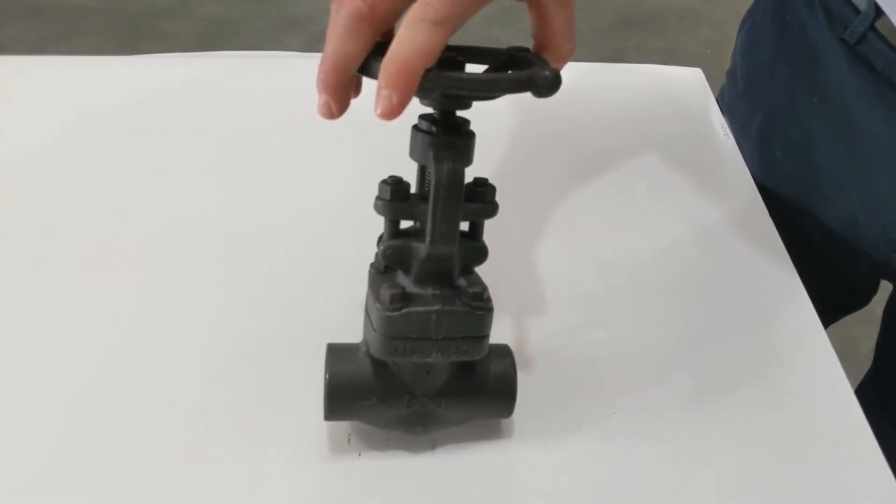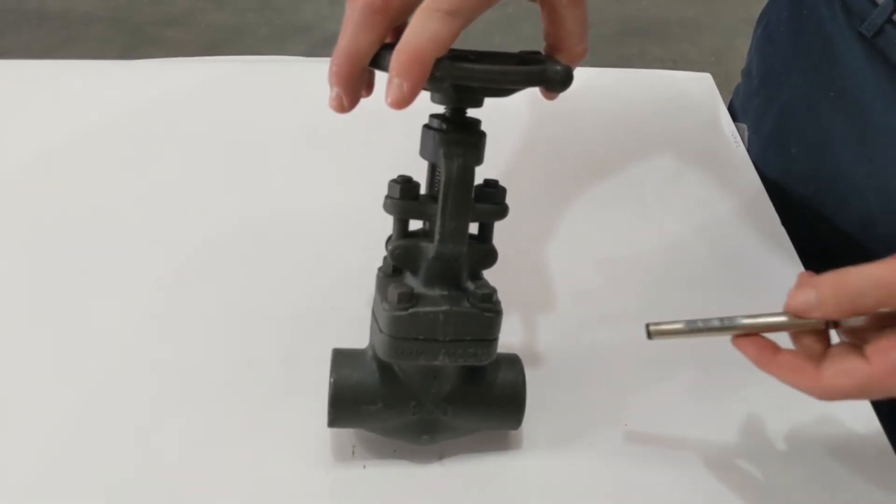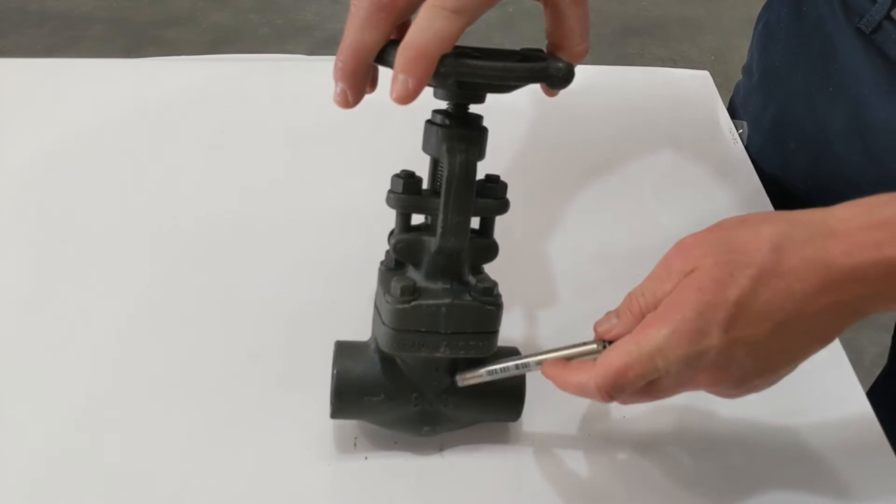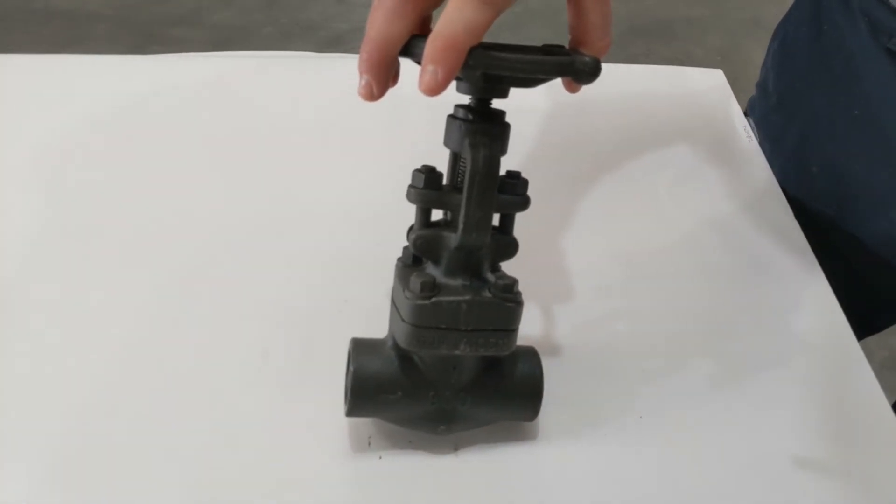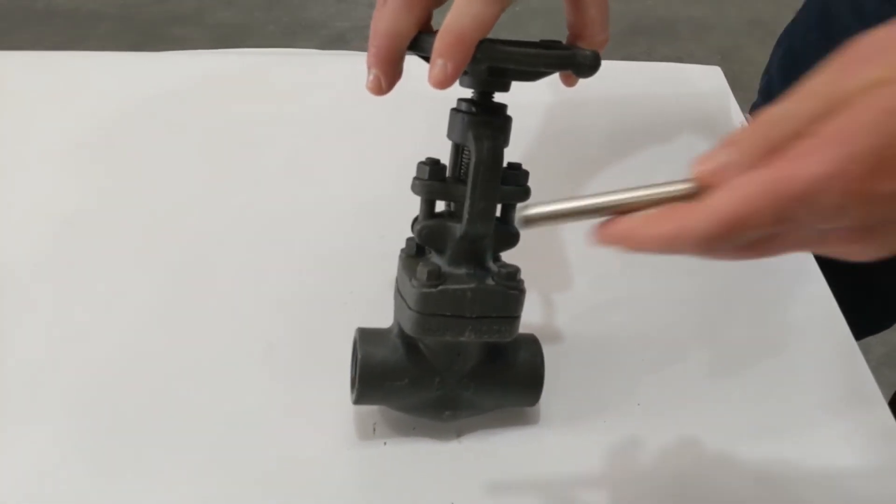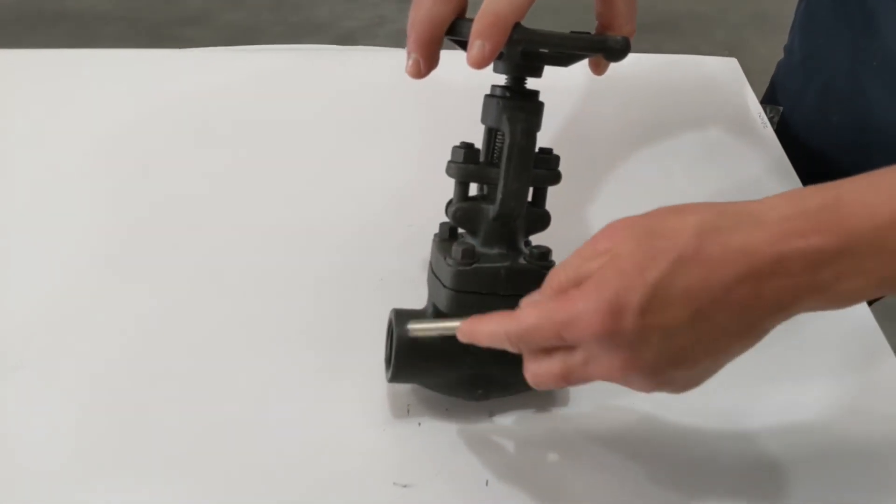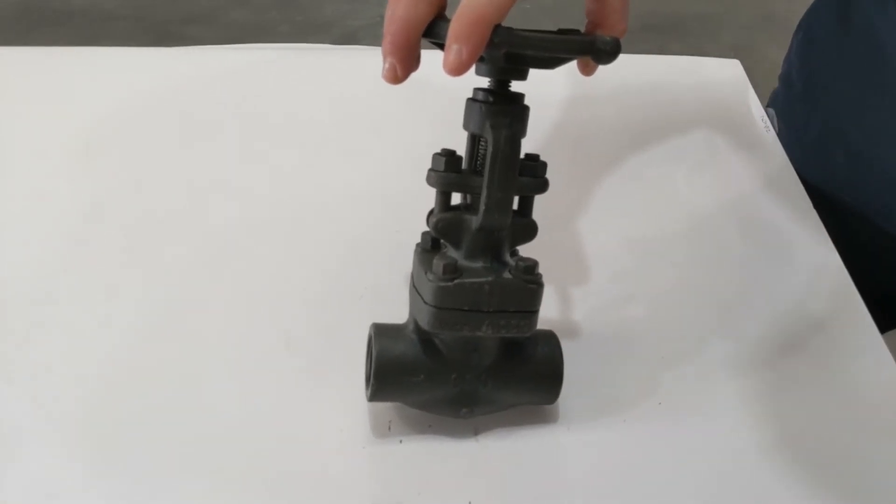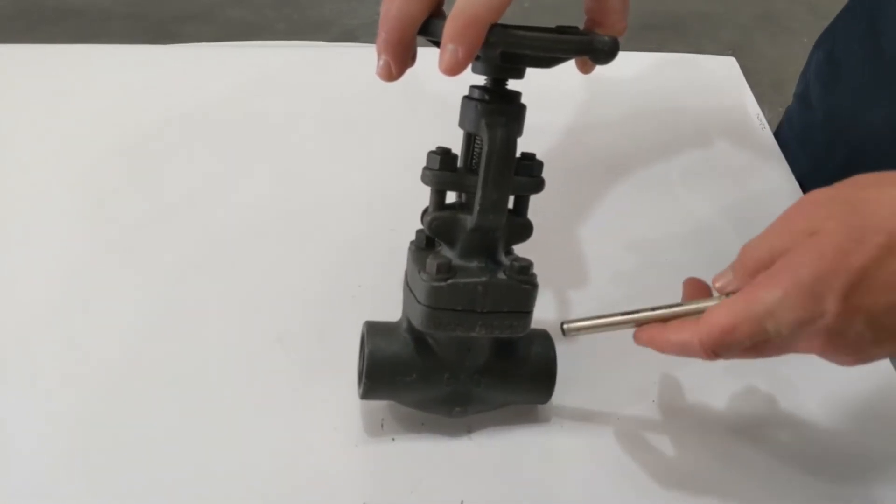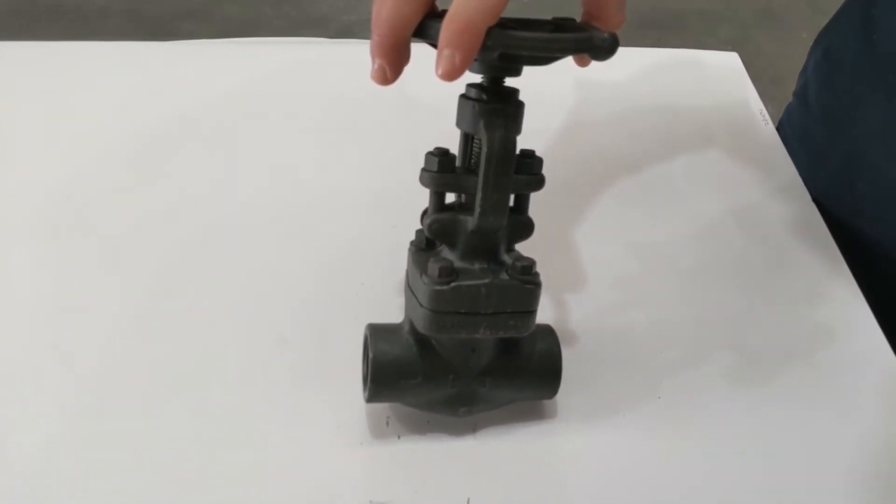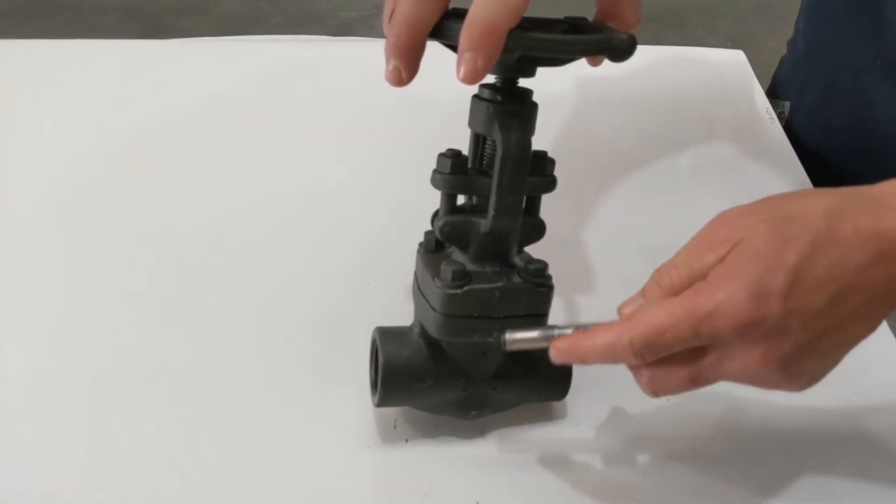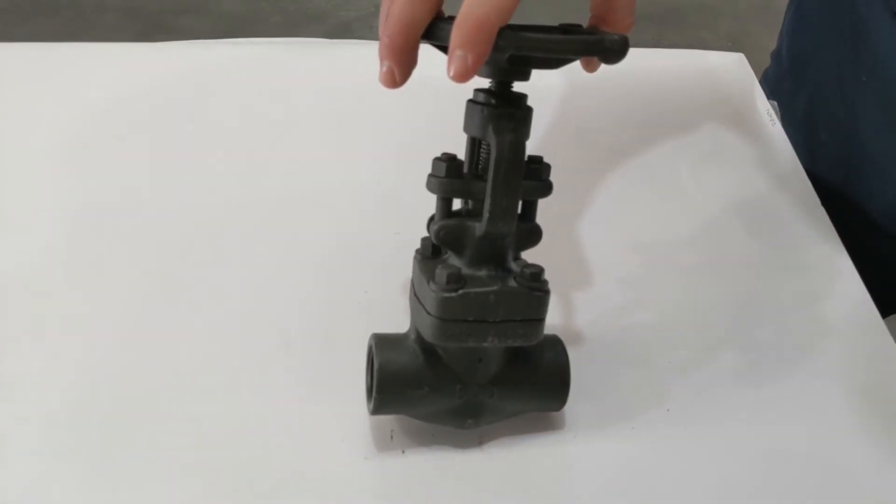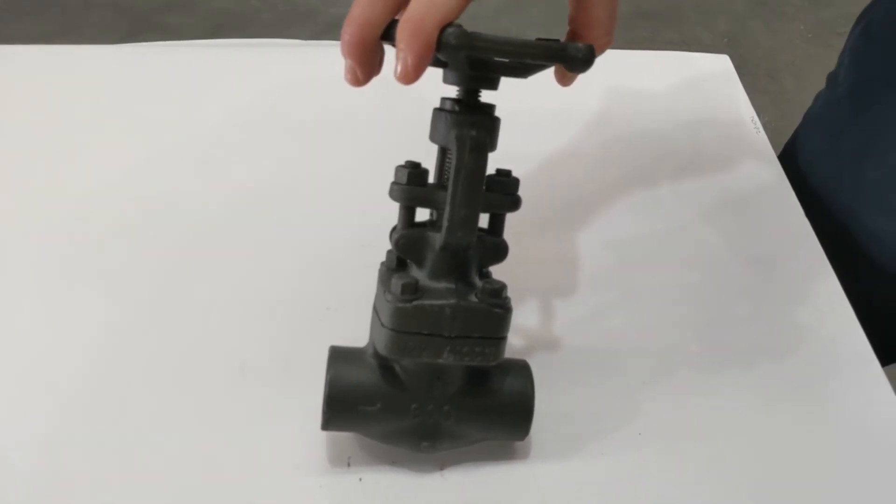That's correct. You can go to the maximum amount of flow this orifice will let through. It's not a large flow like a ball valve would be where it's completely open—it's got to come up and over the seat still, so you still get turbulence in the flow. But it's good for throttling because it's more proportional than say a ball valve or a gate valve.